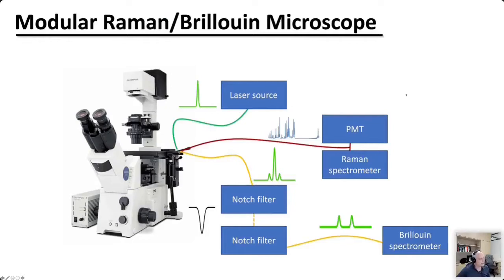If you want to measure this, we need a modular system. We need a laser source, which is not very surprising, but after that we would have a Brillouin spectrometer that acquires the spectrum for every pixel position — which needs notch filters, and I will explain why. In another channel we would have the Raman spectrometer, or we can have a photomultiplier or any kind of detector that detects the spectrum.